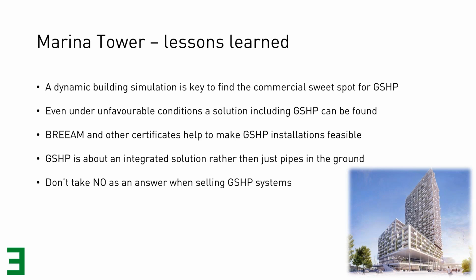My final comment: ground source heat pump is much more about an integrated, often hybrid solution rather than just putting pipes into the ground. It's not enough to put pipes into the ground or into concrete and call it a ground source heat pump system. It has to be an integrated part of the overall solution of the building.